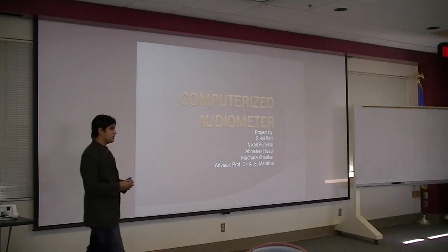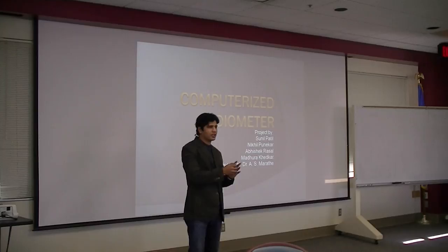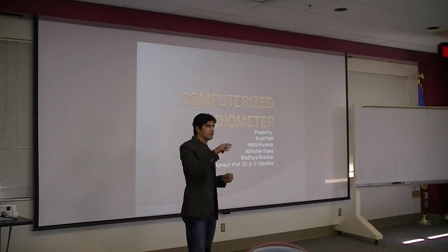Good afternoon, guys. I'm here to present one of the projects that I did, which was a computerized audiometer. The audiometer is a device that is used to plot an audiogram for human beings. The audiogram is the plot of the frequency that you hear against the level at which you hear. It is a plot of frequency against power in dB SL.